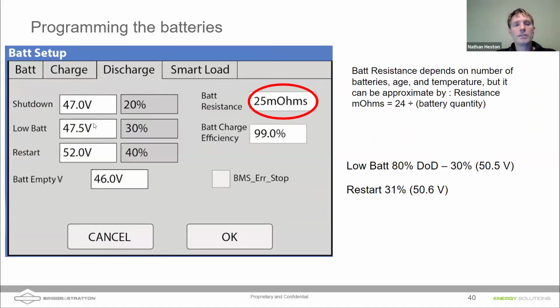The low battery is basically a warning that you'll get on the inverter when you get to low battery. It will illuminate that yellow light on the main screen. The restart voltage is the voltage after we've finished a discharge cycle and we've gotten to low battery cutout, that the batteries will cut back in. So you could call this the cut-in voltage if you like. Again, automatically populated for communicating batteries, but if you're using the Phi battery, a non-communicating battery, we also have an empty battery voltage, and we use this 46 volts here.